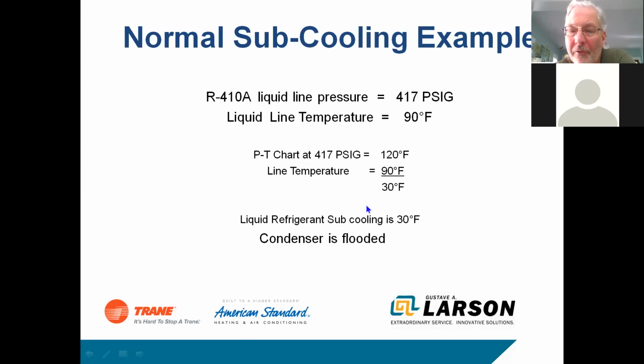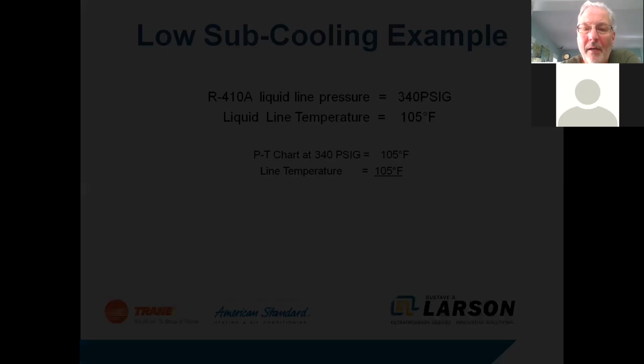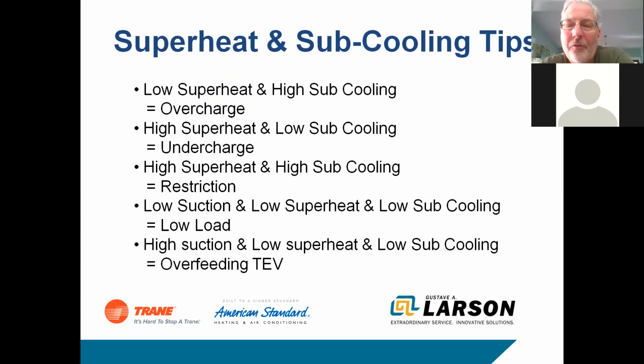So this is a flooded system. This is an overcharged system if you see 30 degrees of subcool, and this is an undercharged system if you see 0 degrees of subcool. Now, there are some rules of thumb. When you're looking at a system with an expansion valve, if I've got low superheat and high subcooling, I probably have an overcharge. If I've got high superheat and low subcooling, it's probably undercharged. We're not feeding refrigerant to that valve. High superheat and high subcool, we may have a restriction in the system.